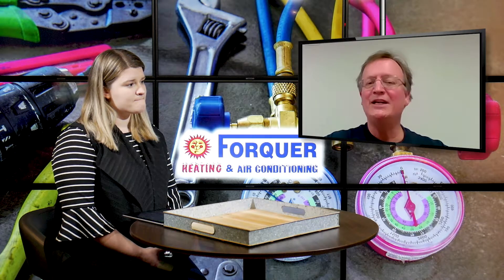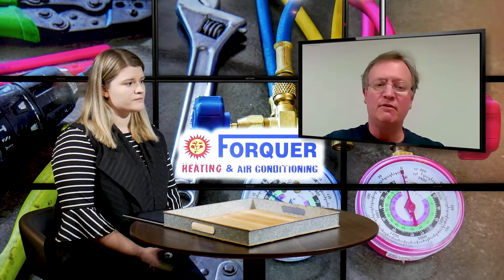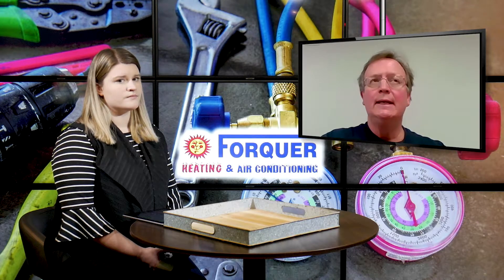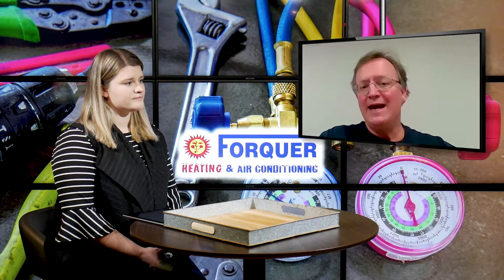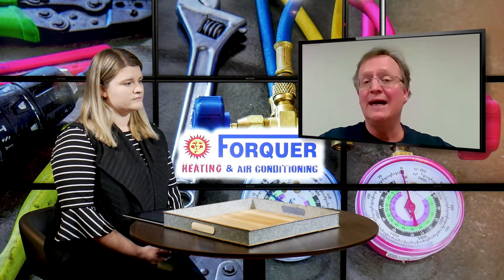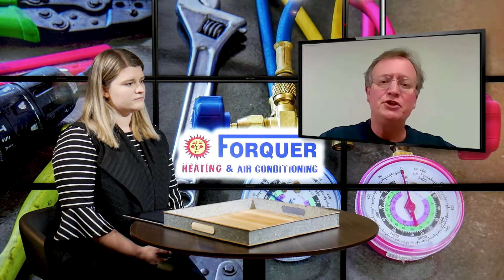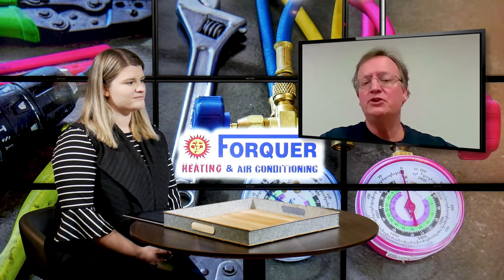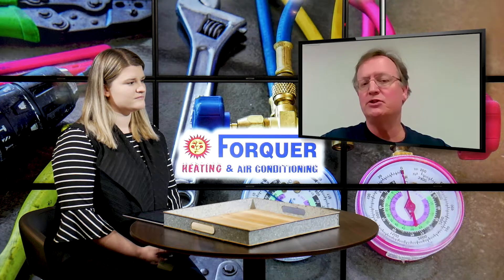I don't really push it with a natural gas furnace, because with a fossil fuel system you get warmer air out of the registers, whereas a heat pump delivers slightly cooler air. For me, the heat pump is all about efficiency, but natural gas is very inexpensive right now with fracking. You can build natural gas furnaces at 95 to 97 percent efficiency, so you're getting the best use out of that natural gas, and the warm discharge off a natural gas furnace is usually preferable over what comes out of the registers on a heat pump.